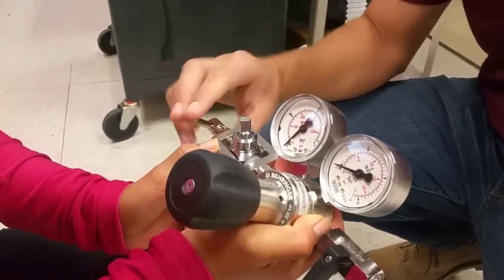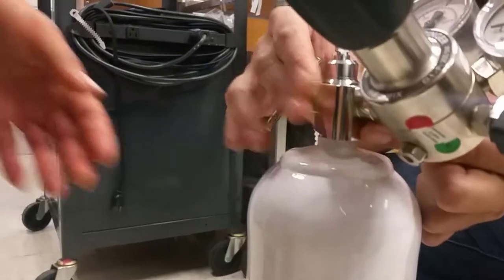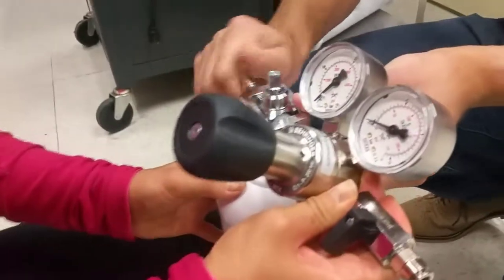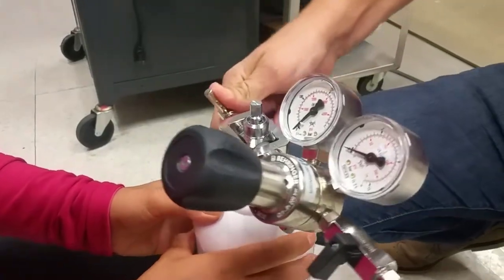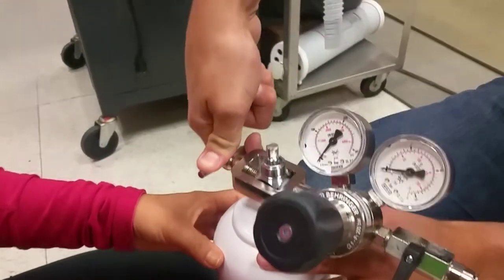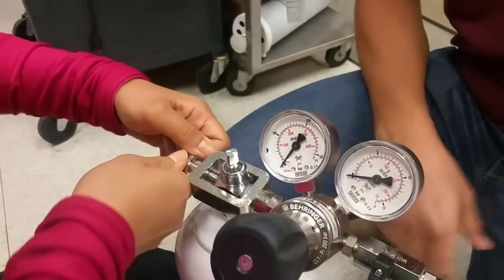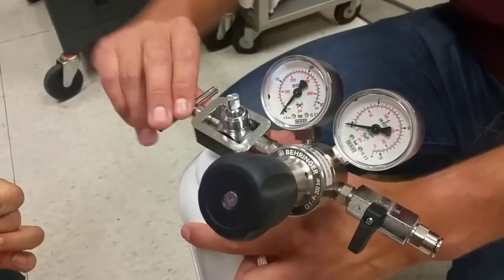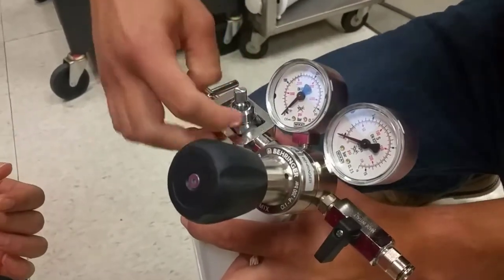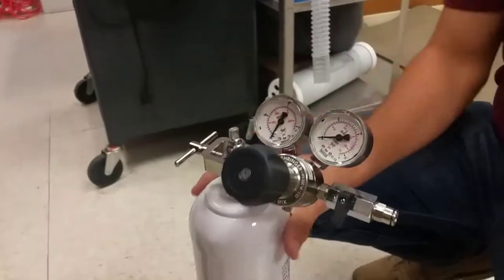So as soon as you get that in contact, you can even just look underneath, make sure the holes are lined up, looks like they are, and then you can just hold it in place and tighten this all the way down, and you'll see it seat right inside of the gasket. And then just turn this until you get a nice snug fit. So, as tight as you can get it. Obviously, we're not trying to crank it down. But you want it tight enough so you don't see any gaps on either side of the washer. So that looks good. We'll just leave that like that.